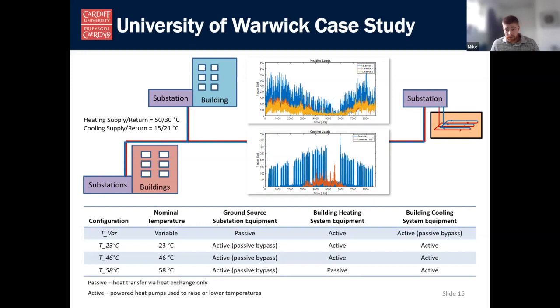For the study, we've considered these 4 configurations based on nominal pipe temperatures. So if we allow the temperature to vary with the ground, as in T-var, we can use passive equipment at the ground source substation, active equipment for building heating, and have the opportunity for using passive building cooling. Whereas if we have a high nominal temperature, as in T58, then we can have passive equipment for building heating, but need heat pumps installed at the ground substation and chillers for building cooling. And for the 2 intermediate configurations, we would require active heating or cooling equipment in all 3 areas.